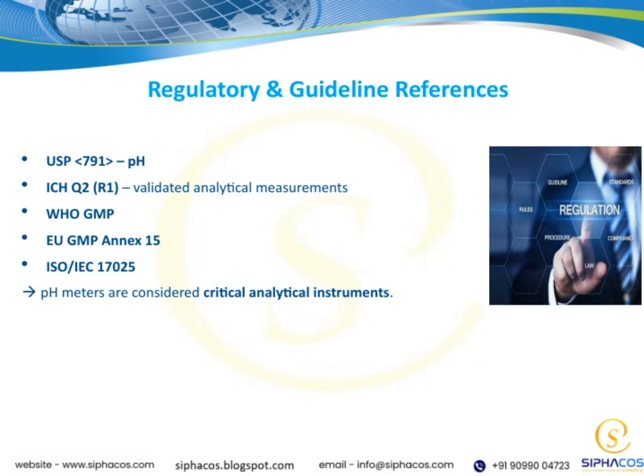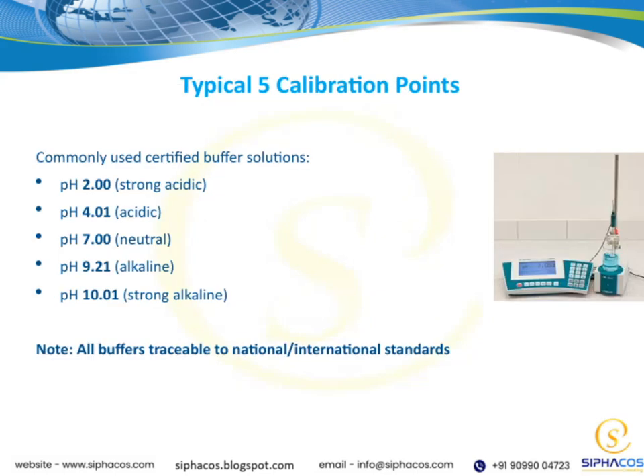A critical point to remember is that pH meters are considered critical analytical instruments. Their accuracy and reliability are essential because they directly impact the quality of our products. Ensuring compliance with these guidelines helps us maintain high standards and supports the overall integrity of our analytical processes. Let's take a closer look at the typical 5 calibration points we use in pH measurement. These are standard points that help us ensure our pH meters are accurate across a range of conditions.